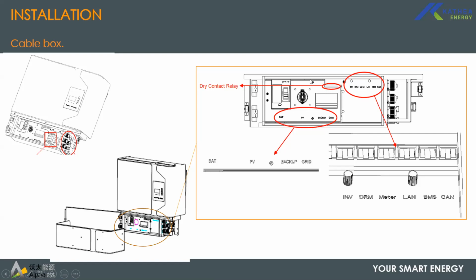And then going to the left, there is an area where there are isolators and breakers. So you get two breakers, which are the backup and the grid. And then you get your PV isolator, labeled PV switch, and then you get your battery breaker, which is a big black one, written BAT, the abbreviation for battery. And then the power cables from the battery are connected on the left side of the inverter. It's a push and plug connection. The cables are supplied together with the inverter.